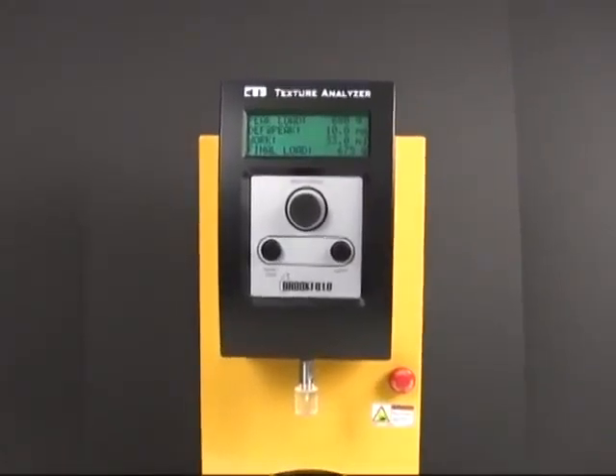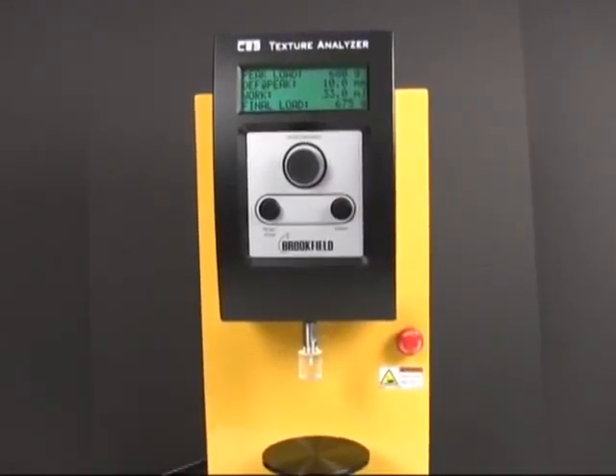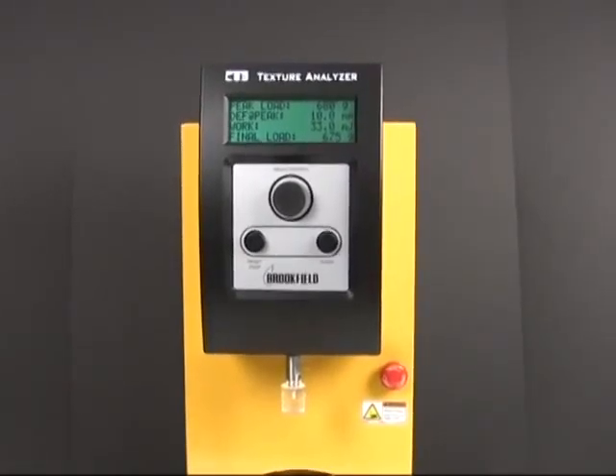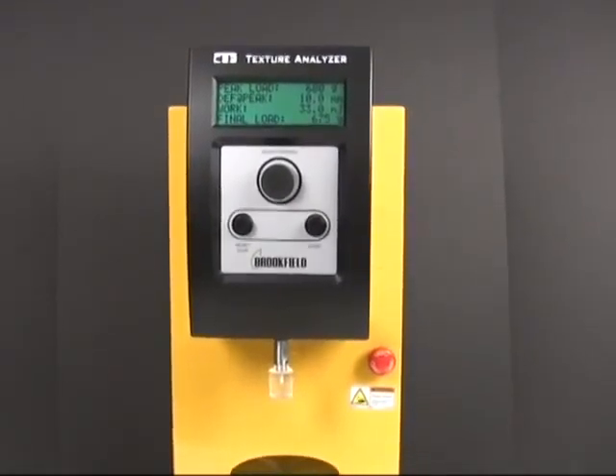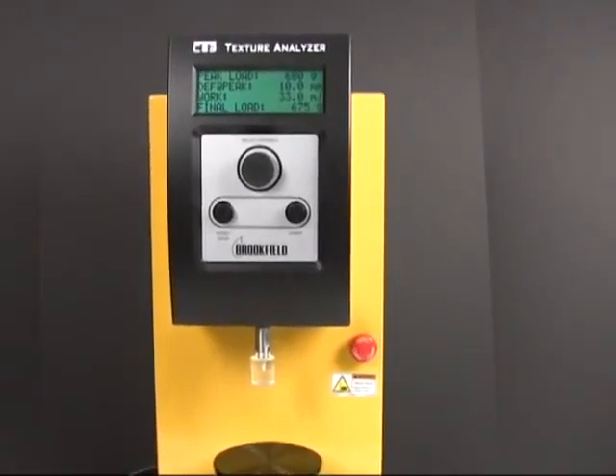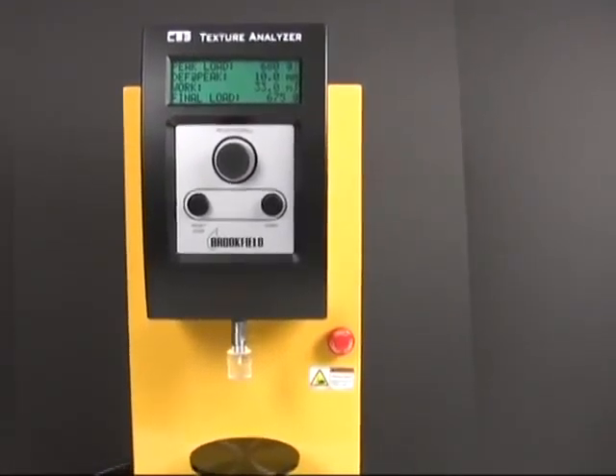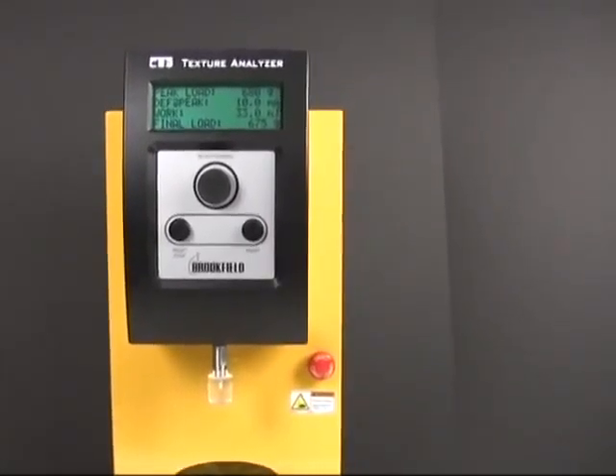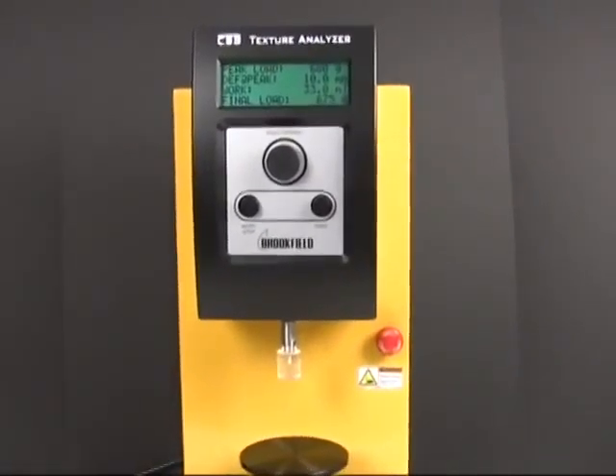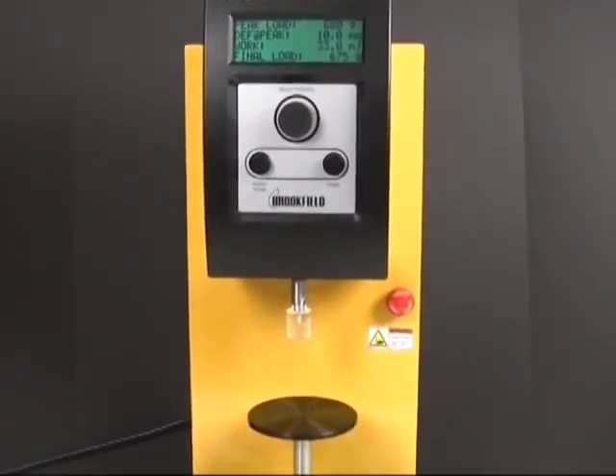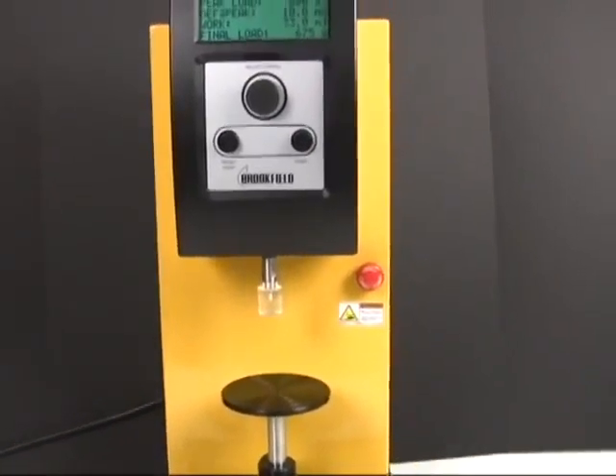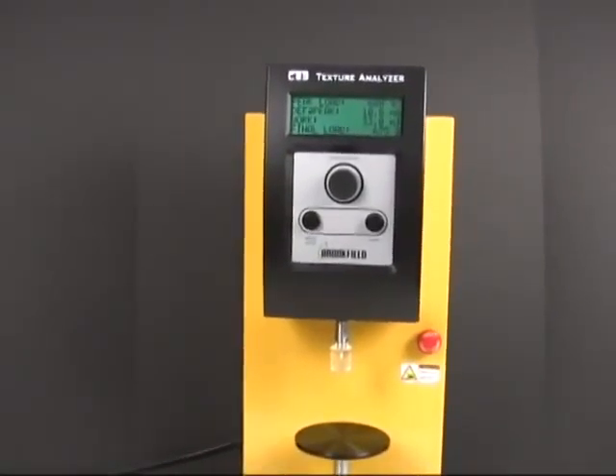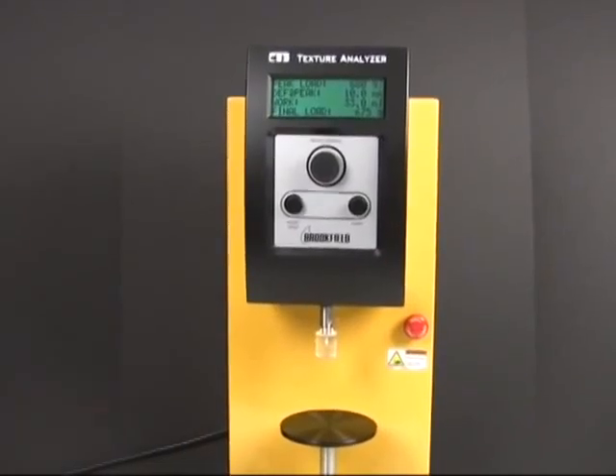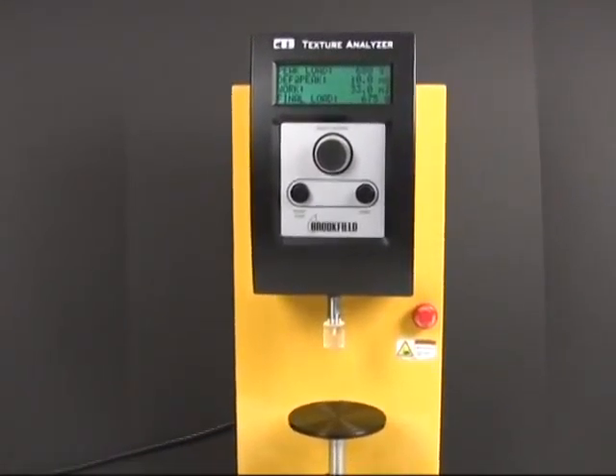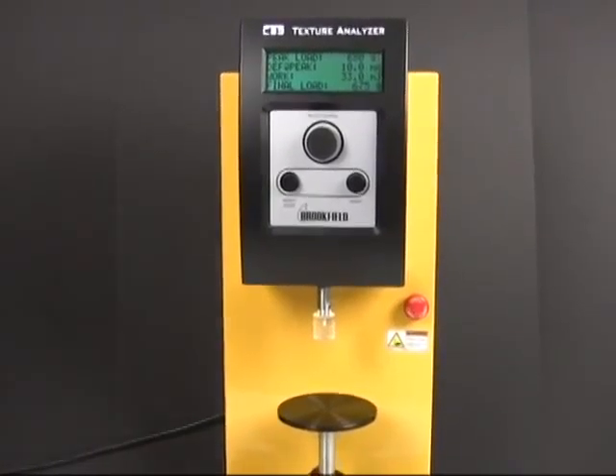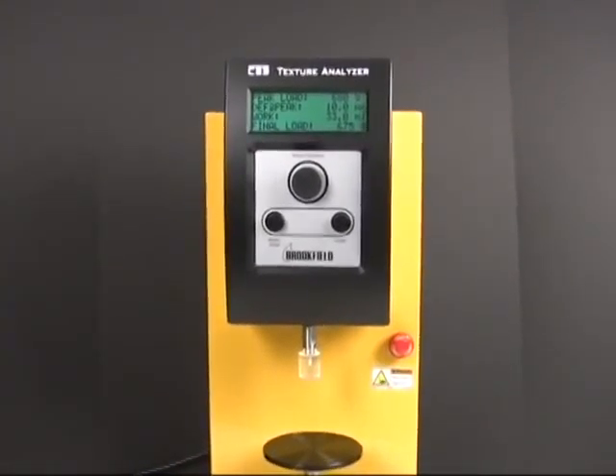This is an issue for medical device, food, gel, cosmetic, and a couple other industries that standards actually require the instruments being calibrated before tests and after being moved. So, in all, I would have to advise not using this instrument in any FDA-supervised industry. The Brookfield CT3 is the definition of a low-budget texture analyzer. Compared to its competitors, it's half the price, but barely a tenth of the value in terms of flexibility, functionality, and for the most part in time, it has trouble meeting basic standards.